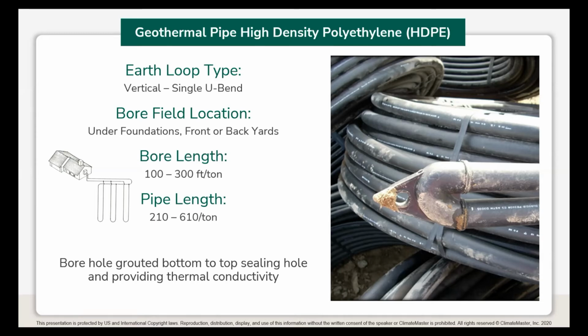It doesn't deteriorate. So the deeper we go, the larger diameter of pipe that we would need to use in your yard. So if we are confined or constrained because of a backyard footprint, but we need to get 900, 1,000 linear feet of borehole in the ground, we could do 5 200-foot boreholes, 15 feet apart or so, or we could do 2 500-foot boreholes, accomplish the same thing, do a little bit different diameter, larger diameter pipe, and then our pumping requirements may be a little different as well, but essentially that's the same heat exchanger buried in the ground.